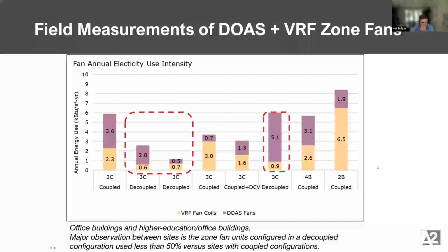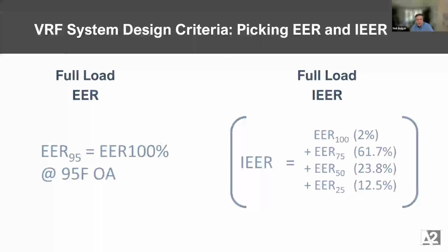And just some proof, this is some field data where the main key takeaway, the tan, these are, each site is a different field site. The tan number is those VRF fan coils. And I've highlighted ones that were decoupled, and you can see the EUI of the fan coils is a third of the other sites, that even where we had a few with DCV, this is a classroom building, it didn't get as low as a fully decoupled system where if there's no heating and cooling, the fan coil just goes off. So, all right, so that's something to consider, right? Like how we configure it. The next thing that I think is always a challenge is there's these metrics, right?